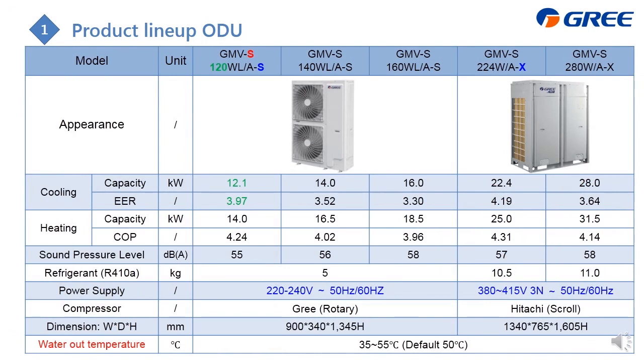This table is the outdoor unit specification, and here is the model. Just like what I said, we have two types, which are the side discharge and the top discharge. From this model you can find that this S means it is the home series, and this value, for example 120, means the cooling capacity, which is 12.1 kilowatt. And the L means it is side discharge, and if there's no L, like this one, it is the top discharge. And the last alphabet means the power supply. Here, S is for single phase and X for three phase.